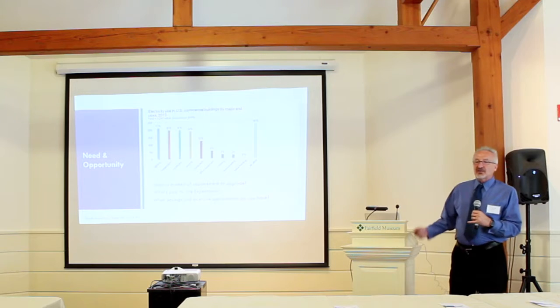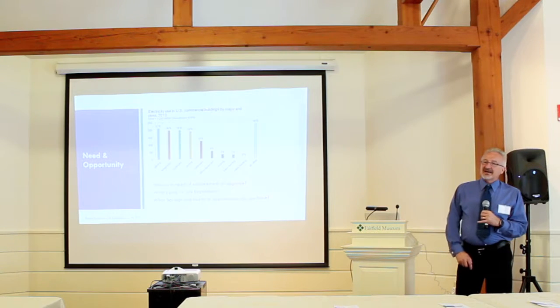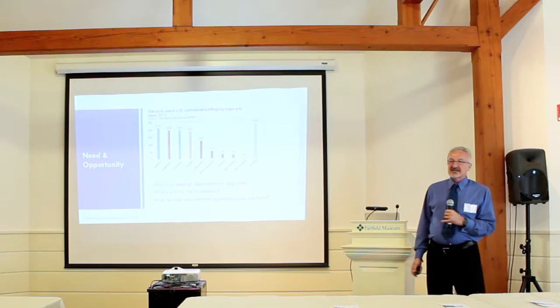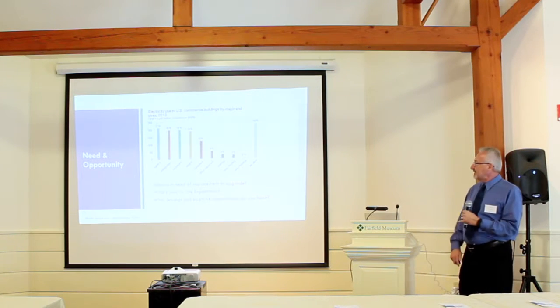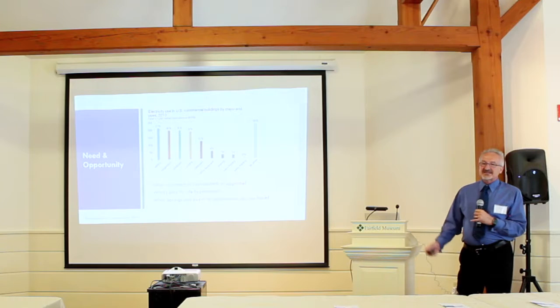We're going to look at where the need is. So we're going to go through the roof: is there a rooftop unit that's 12 or 15 years old? Boilers? A control system that's obsolete and not functioning? You have pneumatic systems; most pneumatic systems are 50, 60% inoperable.